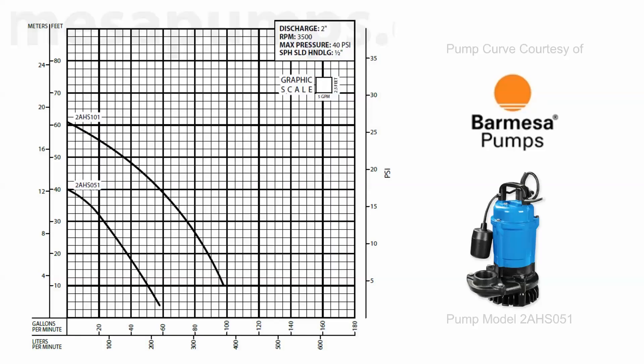Let's take a look at a real pump curve. In this particular example we have a Barmesa pump curve. This is a curve for the 2AHS series pumps — it features both the half horsepower and one horsepower performance curves of these particular pumps. It's pretty interesting to see how from half horsepower to one horsepower you're increasing both the pump's maximum pressure rating, which is indicated on the left-hand side by feet and meters.